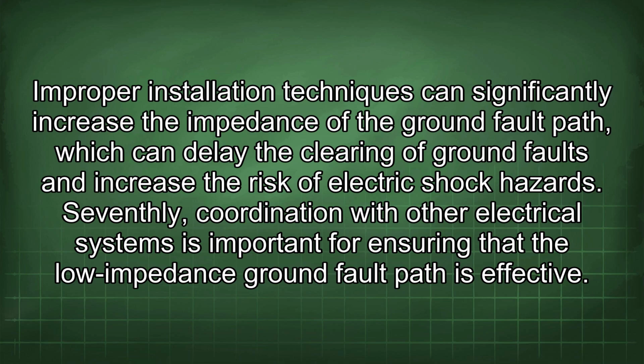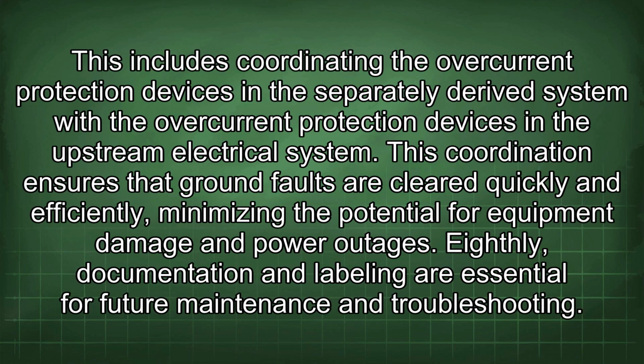Seventhly, coordination with other electrical systems is important for ensuring that the low impedance ground fault path is effective. This includes coordinating the overcurrent protection devices in the separately derived system with the overcurrent protection devices in the upstream electrical system. This coordination ensures that ground faults are cleared quickly and efficiently, minimizing the potential for equipment damage and power outages.